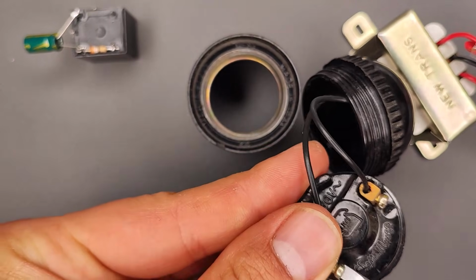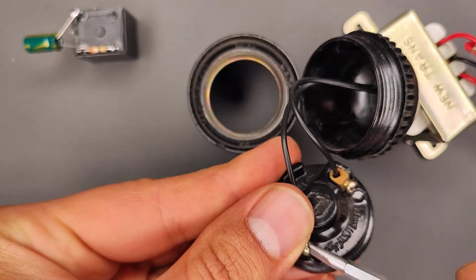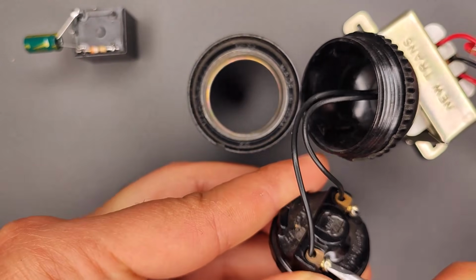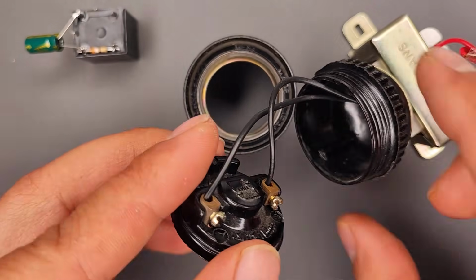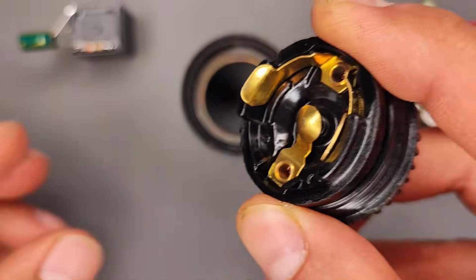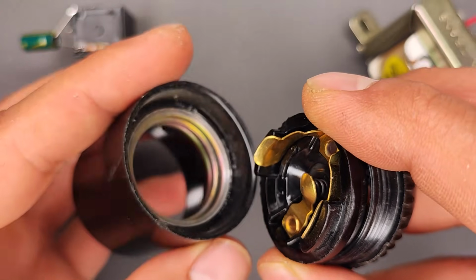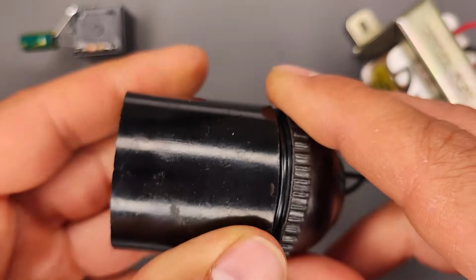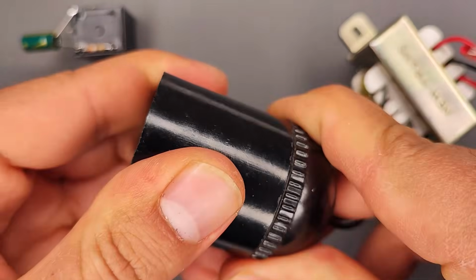The relay produces a low-frequency, irregular, square-like waveform. This causes poor magnetic efficiency inside the transformer. That's why the measured output voltage fluctuates between 160 and 190 volts AC, even with no load.